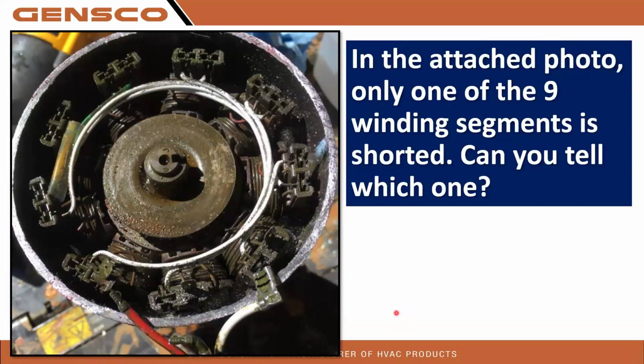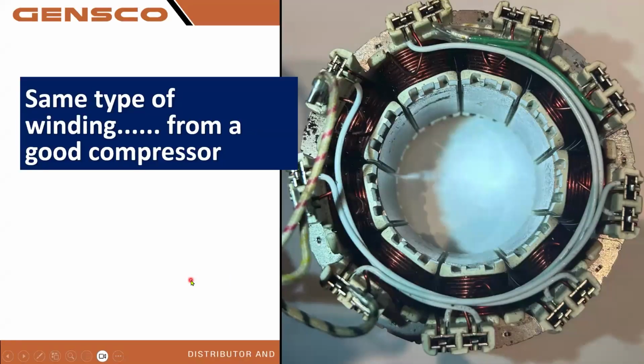Now, in this attached photo, this is an actual unit I cut apart 2 years ago. Only one of those 9 segments is shorted to ground. Can any of you tell which one it is? I'm going to go with no because they all look pretty bad. This is what the same compressor looks like good. This came out of a good, clean compressor. You can see the 3-phase wires connecting to 3 of the posts, and each of those are connected to 2 other posts, giving us a total of 9 segments, 3 per phase.